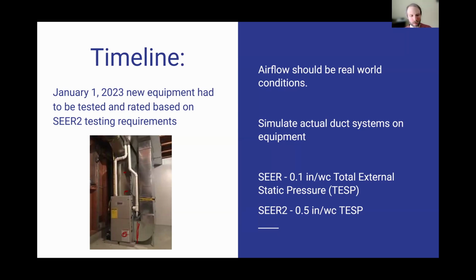And then I guess the next question, and let me know if you're going to cover it: typically there's been a thought that higher SEER equals less dehumidification. Does that play out in SEER2? Has that been fixed? Do you agree with that? Usually when I see an issue with dehumidification, it is based upon improper sizing for the latent load. We oversize for sensible load and drop the temperature of the air faster than we get the latent heat out of the air, so the humidity is left lingering.